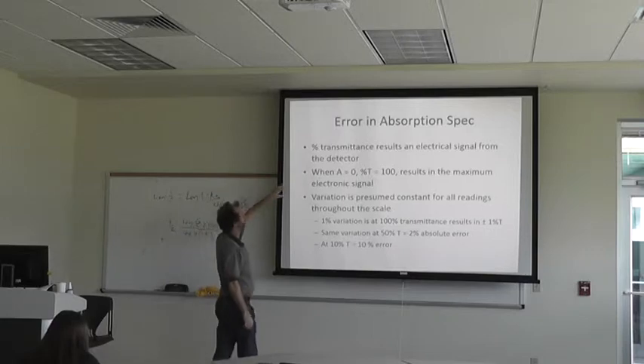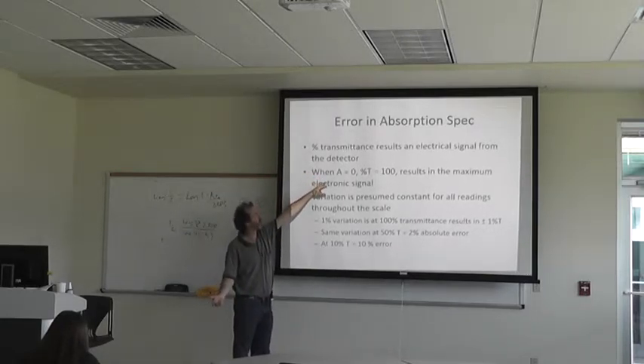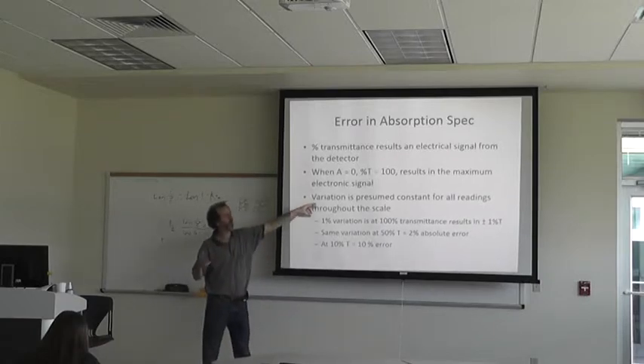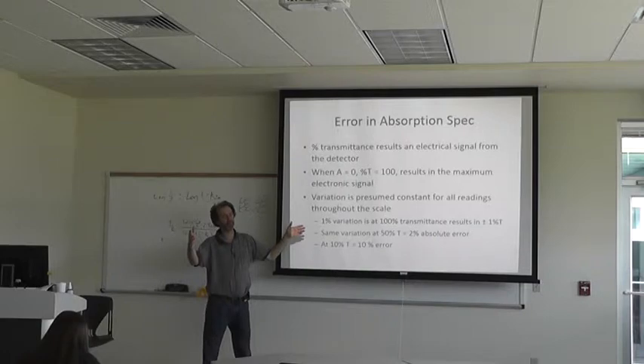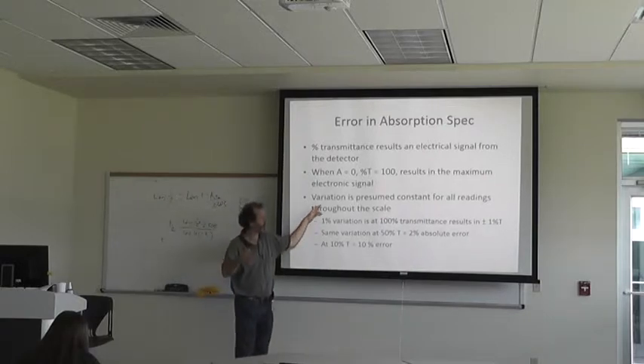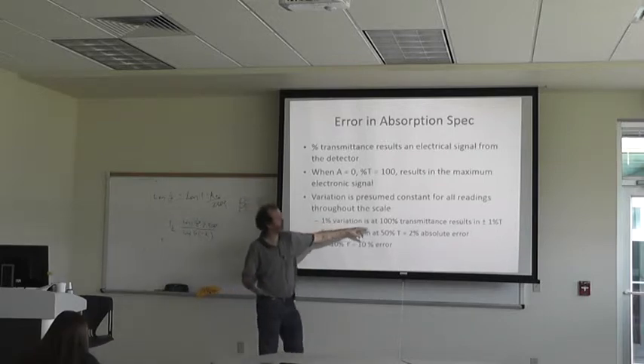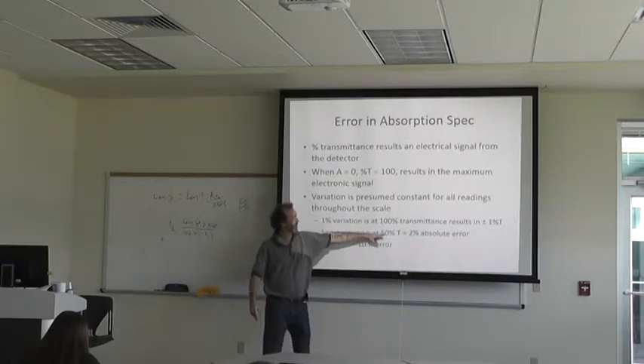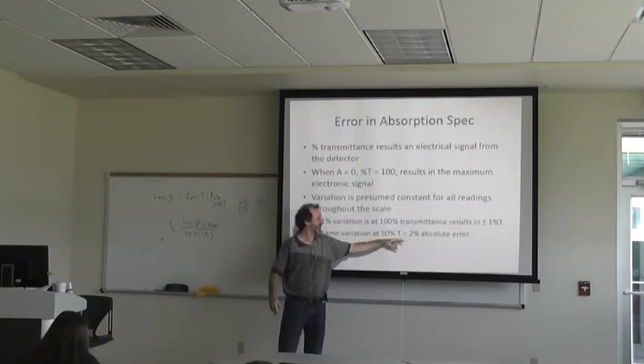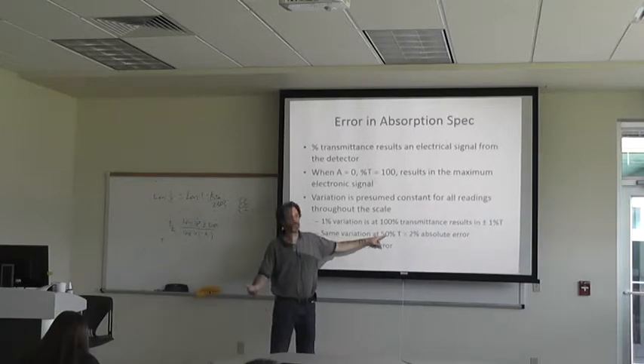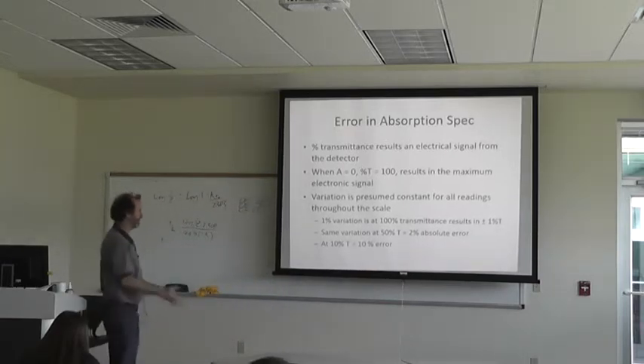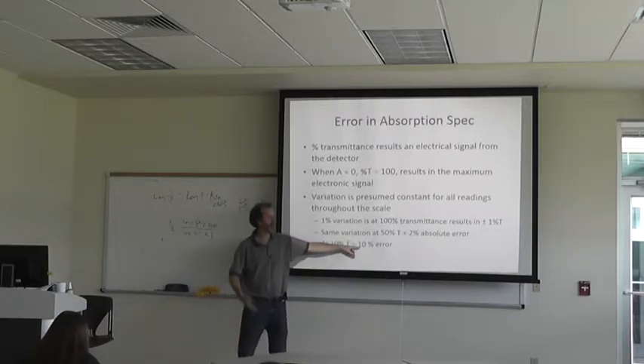Errors in your absorbance spec: the percent transmittance results in an electrical signal from the detector. When absorbance is zero, percent transmittance is 100, which results in the maximum electric signal. The variation in that electrical signal is presumed to be constant throughout the scale from zero to 100%. So a 1% variation at 100% transmittance results in ±1% transmittance. Versus the same variation at 50% equals 2% absolute error, because 1% is 2% of 50% — it basically doubles the error. At 10% transmittance, that makes it a 10% error.